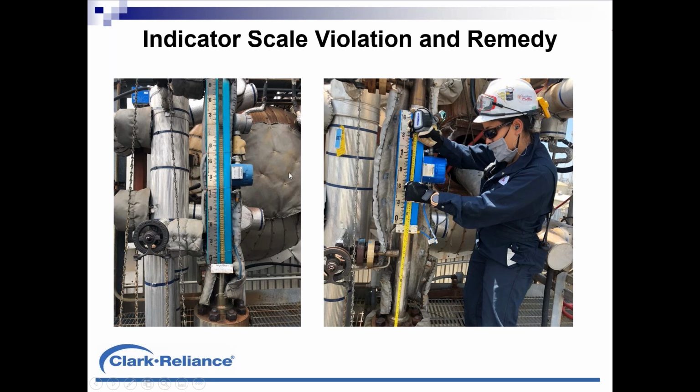So what's happening here on this same application is the technician here has retrofitted a code correct indication scale corresponding to the operating range of the boiler. So we had a problem and it was remedied.